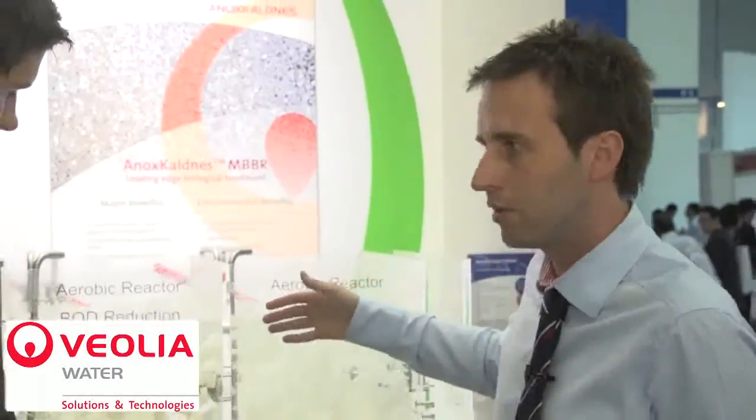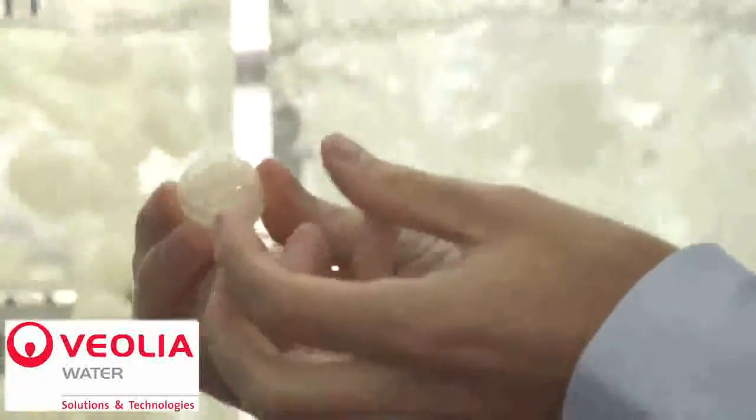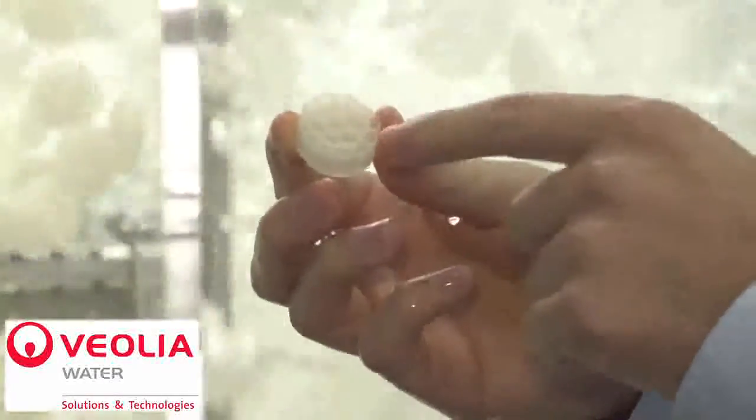The ANITA Mox process is based on the MBBR technology, which we have a demonstration here. We will basically grow the Anammox bacteria using the carriers. The carriers serve as a support for the microorganisms, so we will have a lot of bacteria inside these carriers — that's basically the home for the bacteria. The beauty of this process is that the Anammox bacteria will convert the ammonia directly into nitrogen gas. We don't have the conventional nitrogen removal with nitrification and denitrification, so there's a lot of energy saving and no carbon source needed for that process.